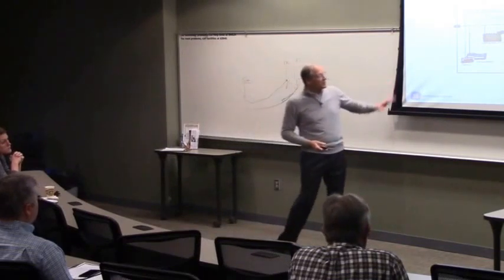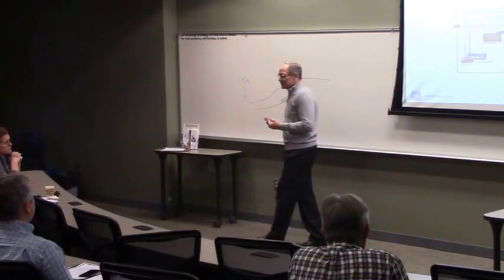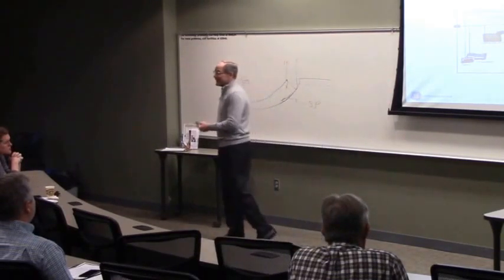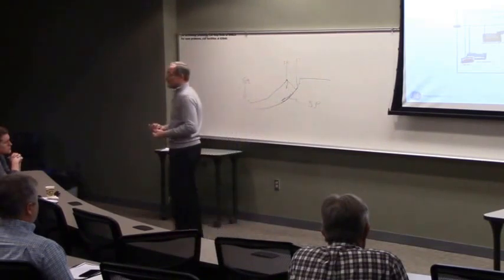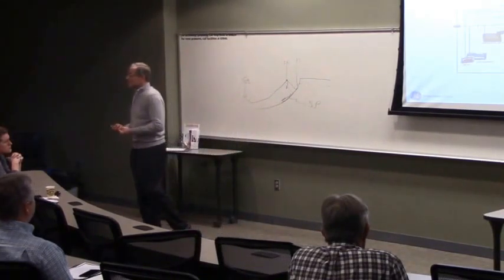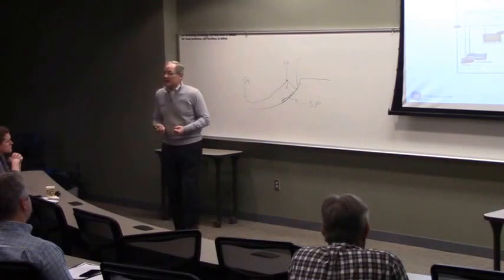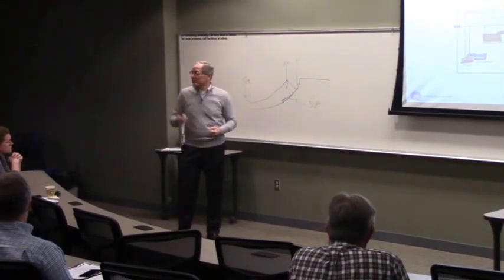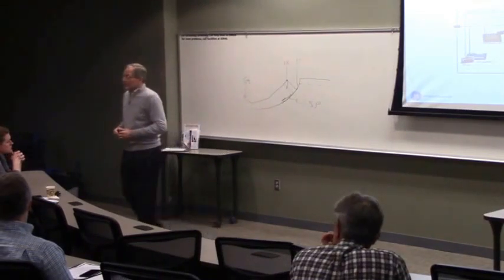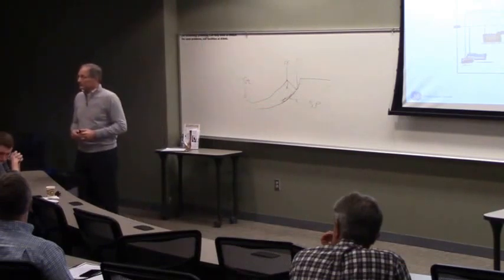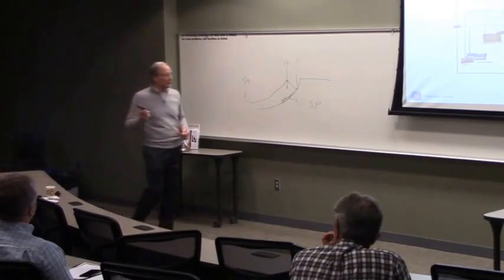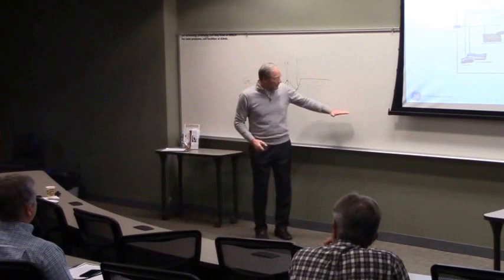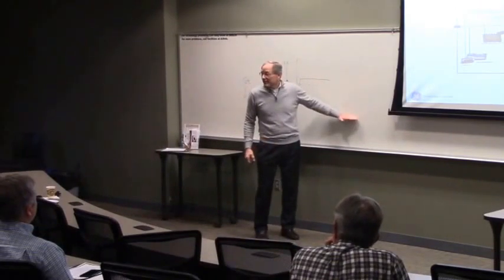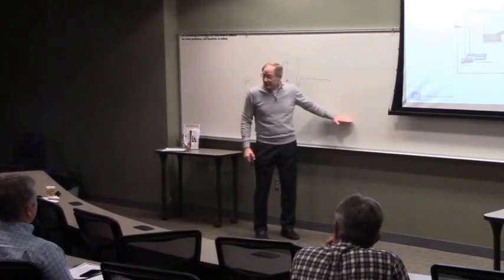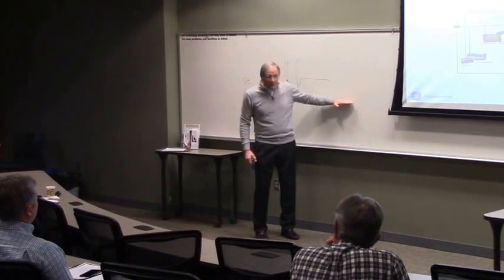So what this does is a low voltage network dynamic grid edge controller that looks at voltage and reactive power as a set point controller. Is this like back-to-back inverters with a better control system? Think of it as a hierarchical control network, where the inverters are here, a number of inverters, and the next level up in the hierarchy are these.